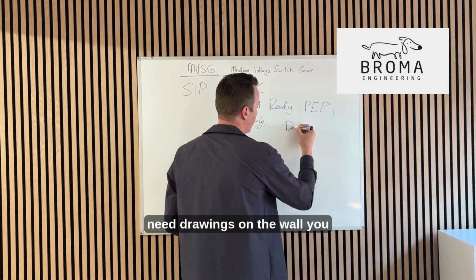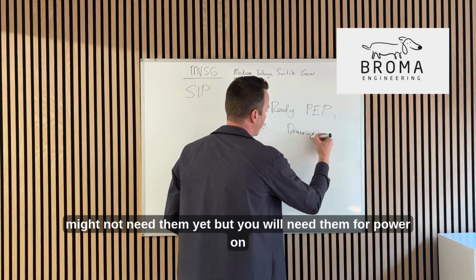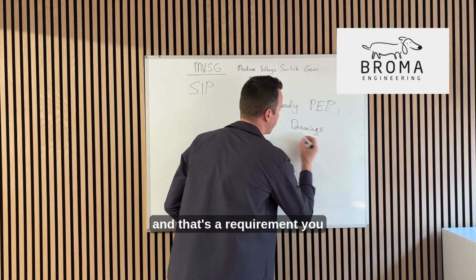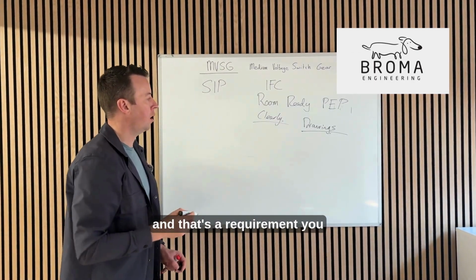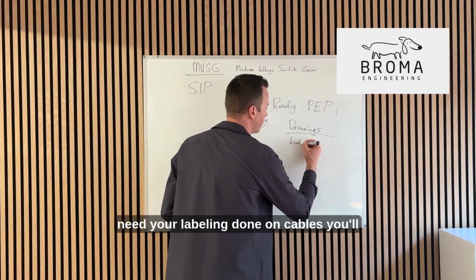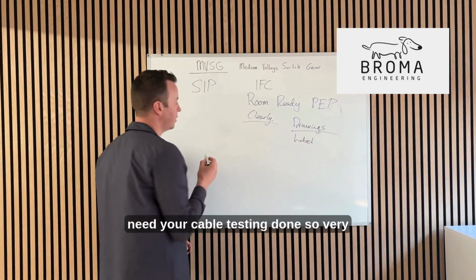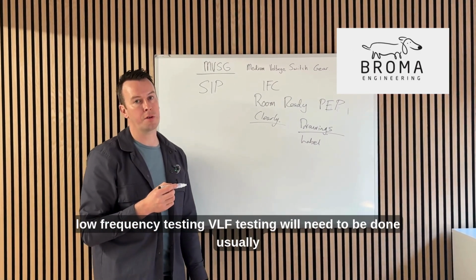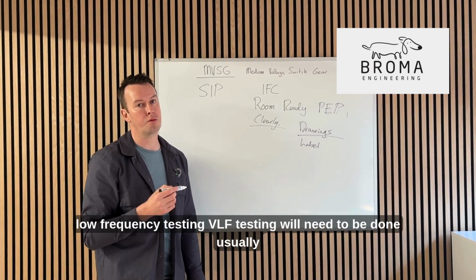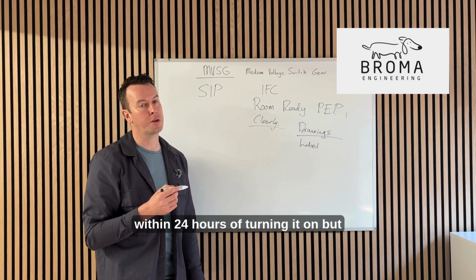You'll need drawings on the wall. You might not need them yet, but you will need them for power on. That's a requirement. You'll need your labeling done on cables. You'll need your cable testing done, so very low frequency testing, VLF testing, will need to be done usually within 24 hours of turning it on.